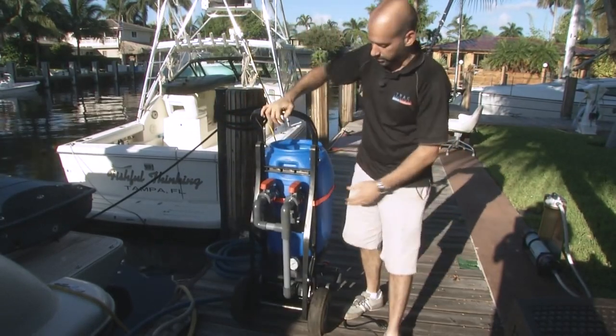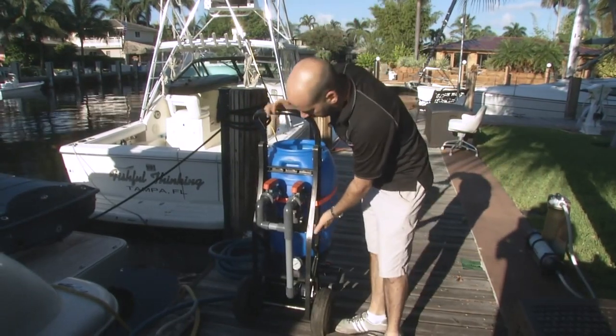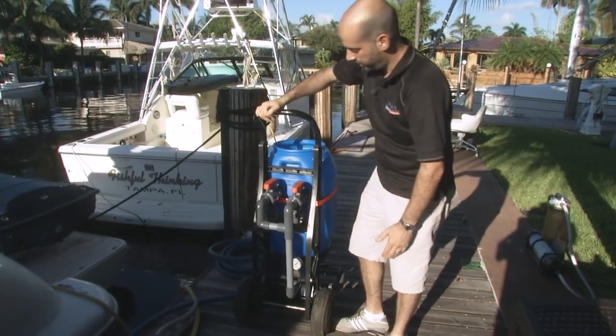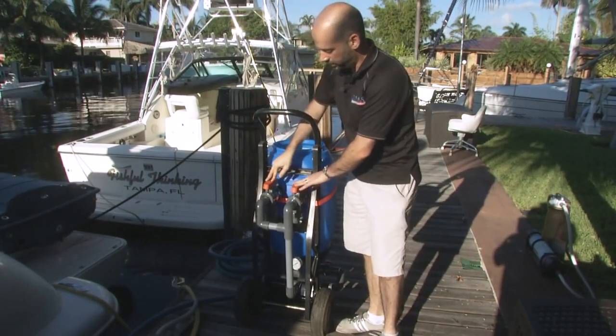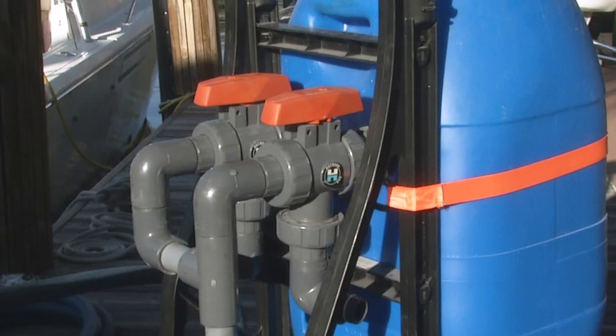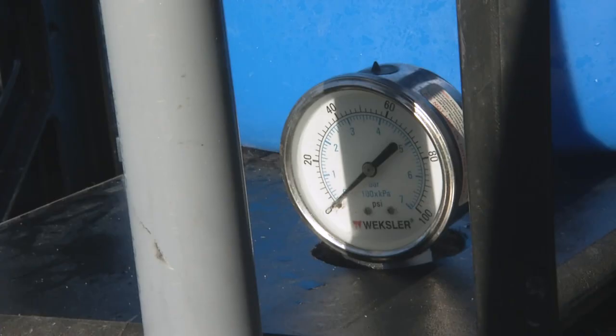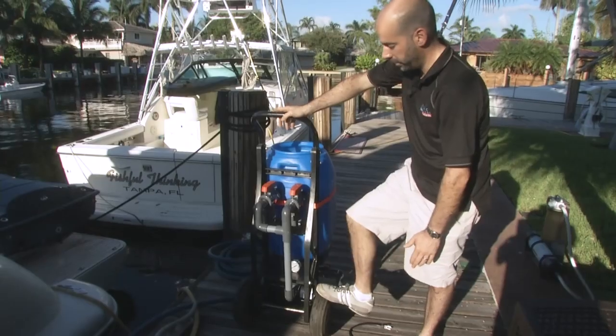One of the other benefits of the Porta-Flush is here is where you connect and return from the system, but it allows you, with these valves here, to reverse the flow without having to remove any of the pipes. You also have a pressure gauge, which allows you to monitor the system during the flush.